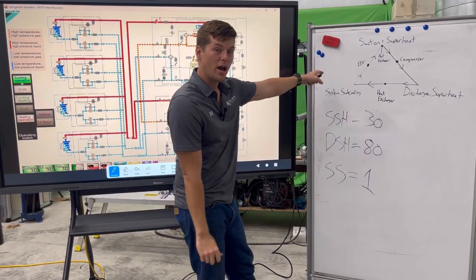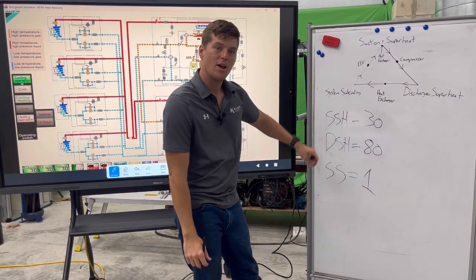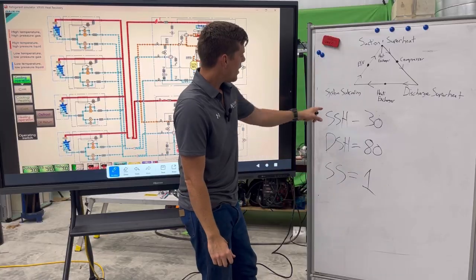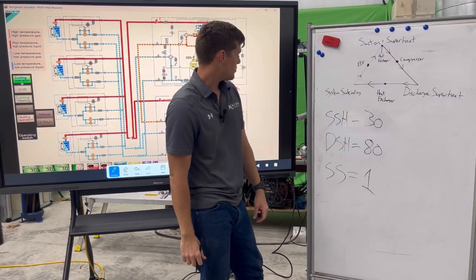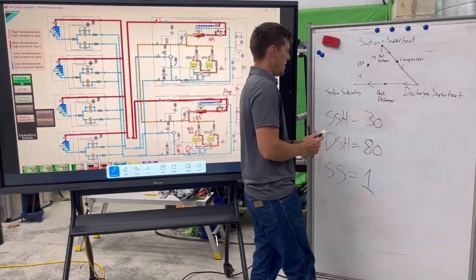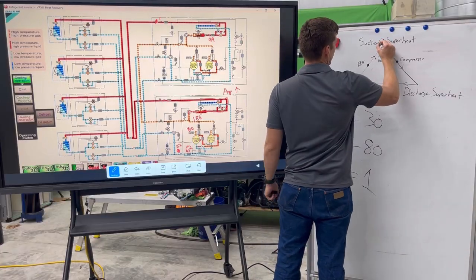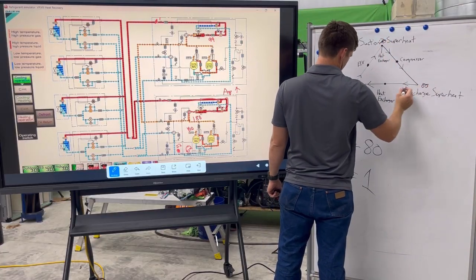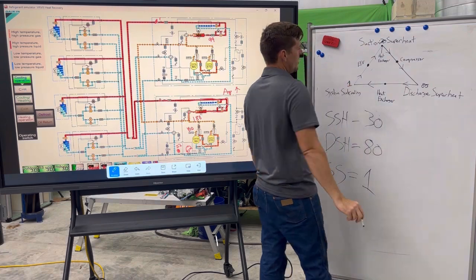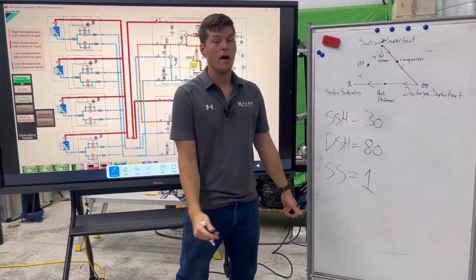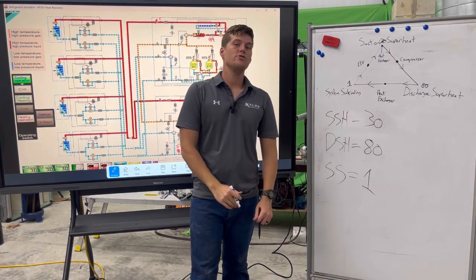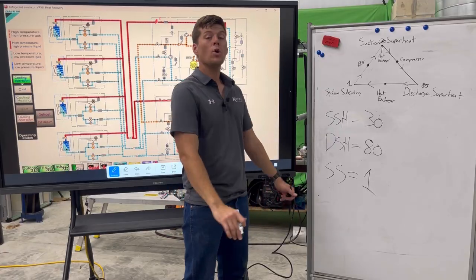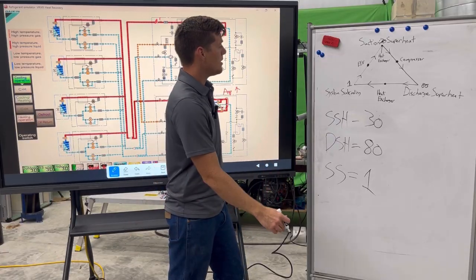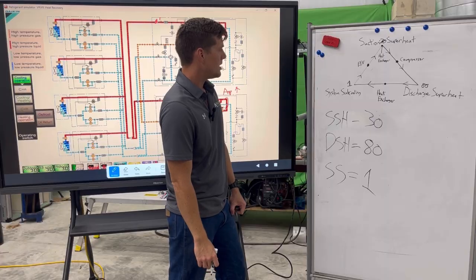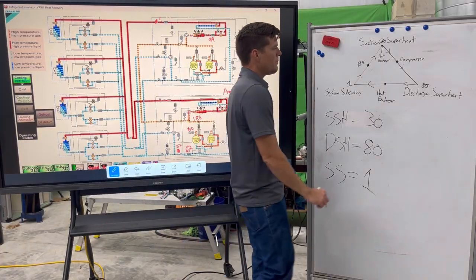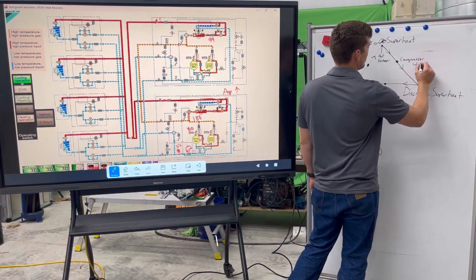This troubleshooting triangle is designed to help you pinpoint where the problems are. When will I hang my hat up on this? Well, where am I going to go next? I built the 3 corners of my triangle. I've got a 30 up here, I've got an 80 over here, and I've got a 1 over here. Now, all 3 of these things point to what? A lack of charge, a lack of refrigerant flowing through the system. What am I missing here? Oh, I'm missing compressor speed. What is my compressor speed? Well, let's say my compressor speed is at 40 RPS.